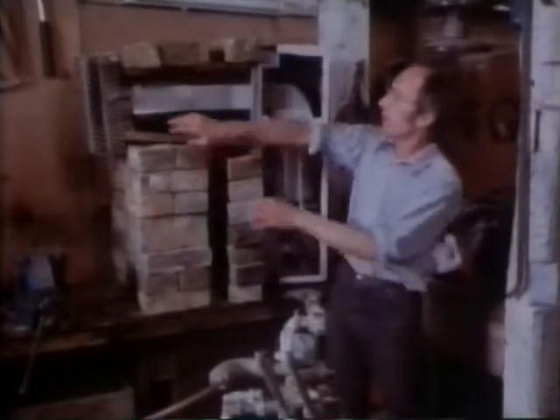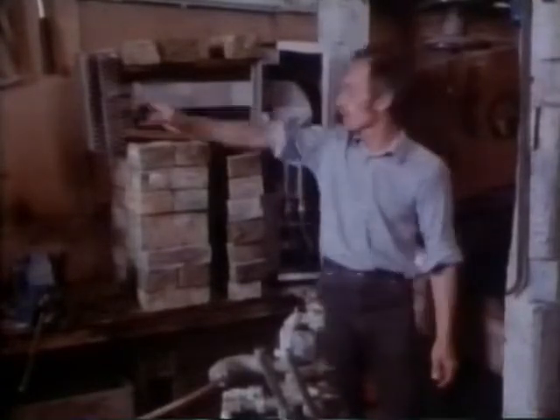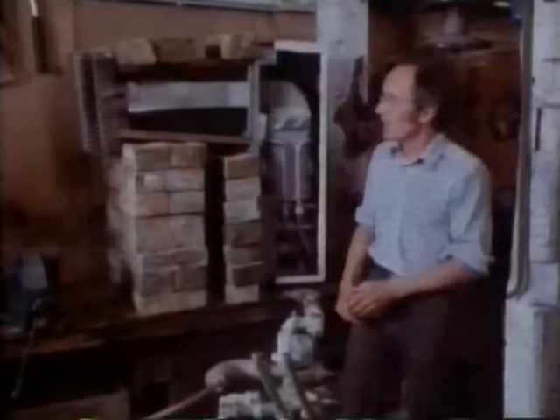Many gas boilers have a balanced flue. This is basically just a hole in the wall — air comes in through this hole, goes around the outside and up through the middle of the boiler, and then the exhaust gases come out through the same hole. Unlike the Norman horizontal chimneys this actually works because the whole unit is totally sealed and the pressure of the air coming in exactly equals or balances the pressure of the exhaust gases coming out — and that's why it's called a balanced flue. It often seems rather wasteful when you feel all the heat coming out of one of these things when the boiler's on, but in fact gas-powered boilers are really quite efficient and up to three quarters of the heat of the fire is transferred to the water. In an open fire only a quarter of the heat may be transferred to the room and three quarters of it may be lost at the chimney.